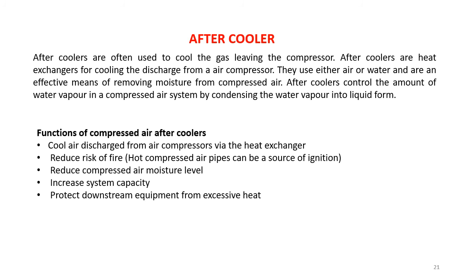The functions of aftercoolers are to cool the air discharged from the air compressor via a heat exchanger, which reduces the risk of fire. Then it reduces the compressed air moisture level, increases the capacity of the system, and protects the downstream equipment from excessive heat. So aftercoolers are very important in the pneumatic circuit.